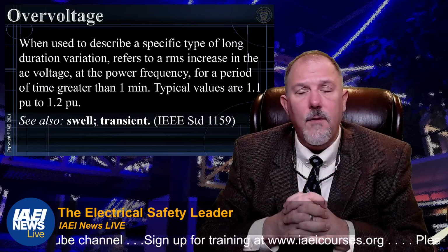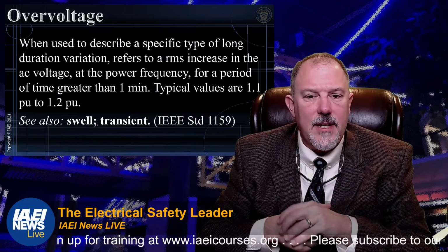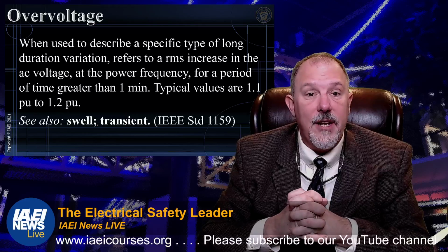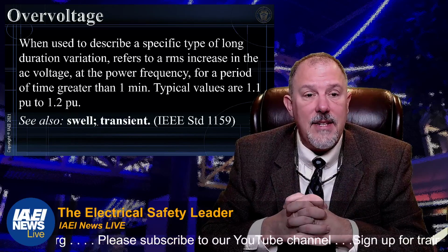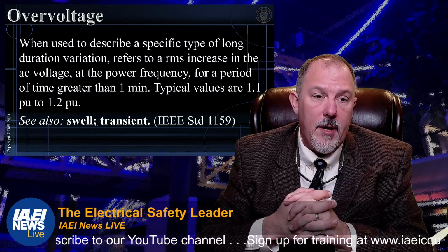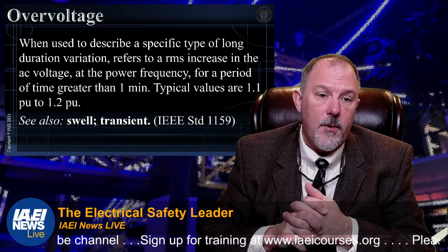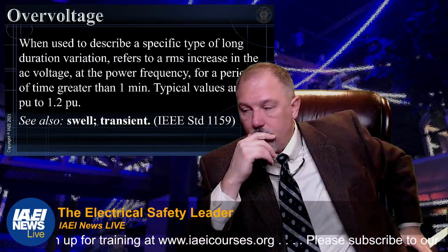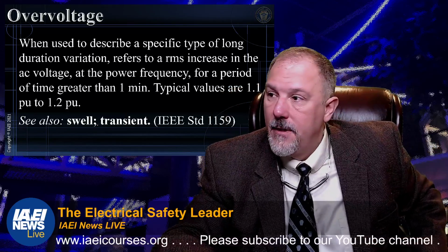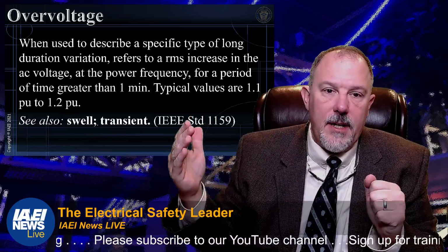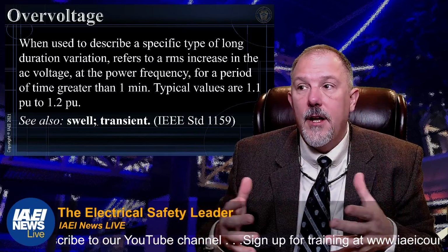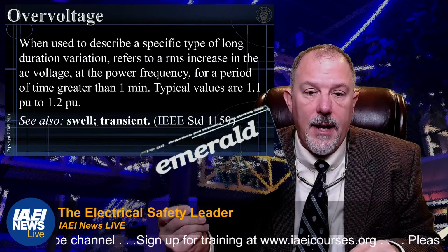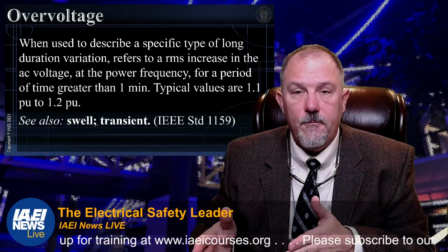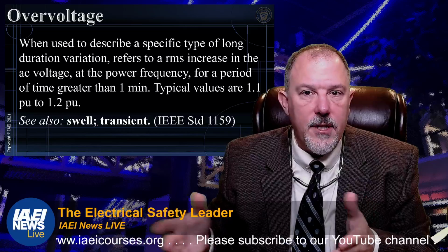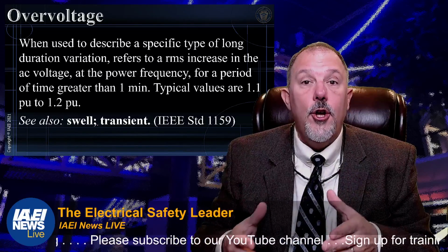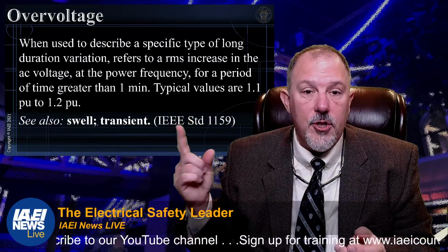So then you have an overvoltage. Now, here's what IEEE standard 1159 says. When used to describe a specific type of long duration variation, it refers to an RMS increase in the AC voltage at the power frequency for a period of time greater than 1 minute. Typical values are 1.1 per unit to 1.2 per unit. So, when I say overvoltage, this is what we typically will reference. If I tell you I had an overvoltage, if you were an engineer and you learned from books like the IEEE Emerald book, and you studied transient events, and you studied other notches and whatnot, because you're looking at sensitive electronic equipment, your perspective of overvoltage is what I'm showing here.